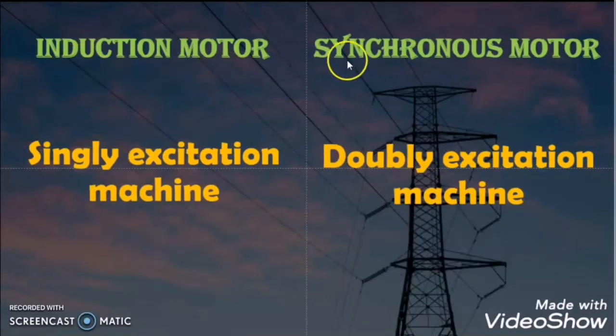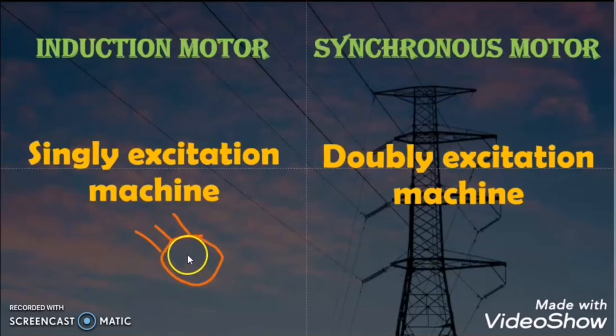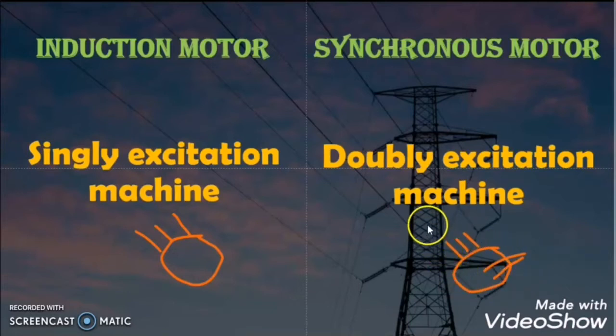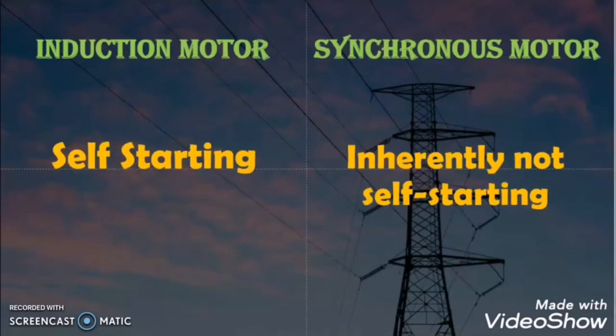The second difference is excitation. The induction motor is a singly excited machine — we give power supply only to the stator winding, and the rotor gets power by induction. But in the synchronous motor, we give two excitations: one AC supply to the stator winding and one DC supply to the rotor winding. So the synchronous motor is a doubly excited machine.